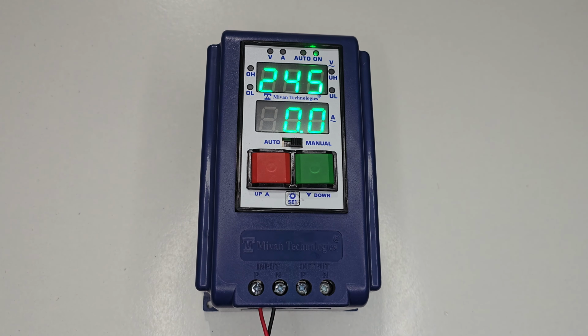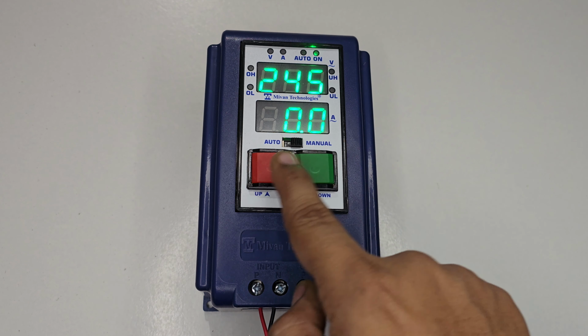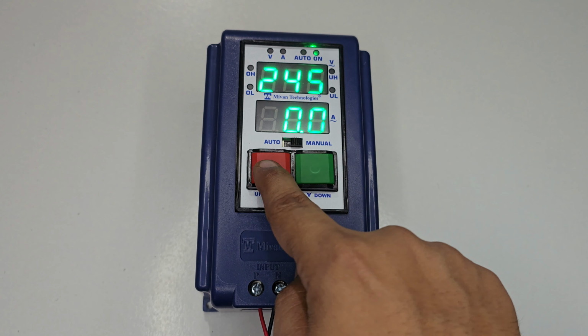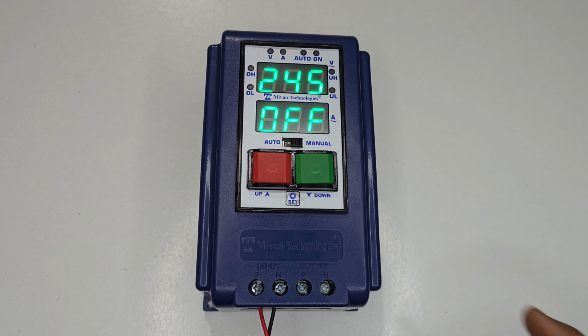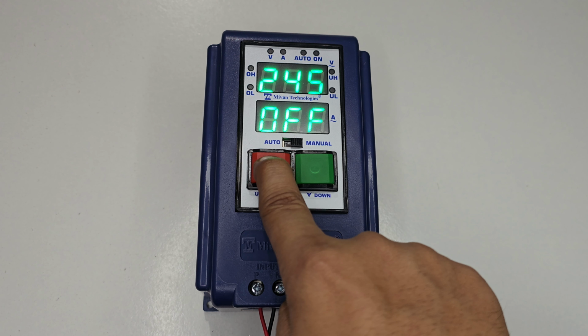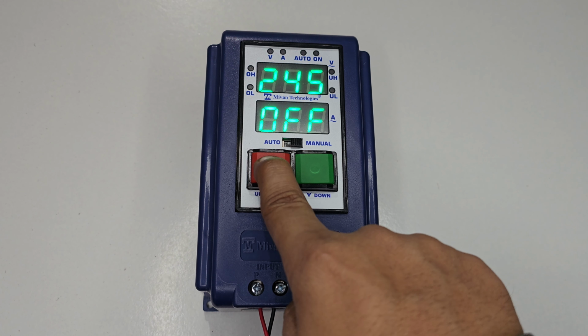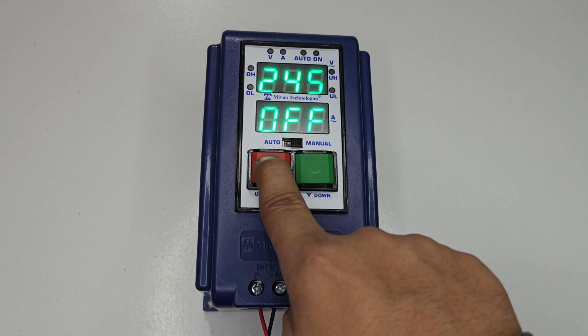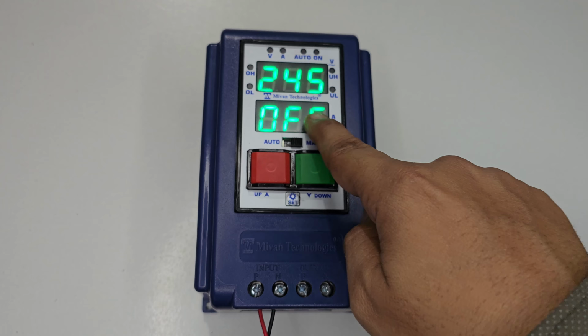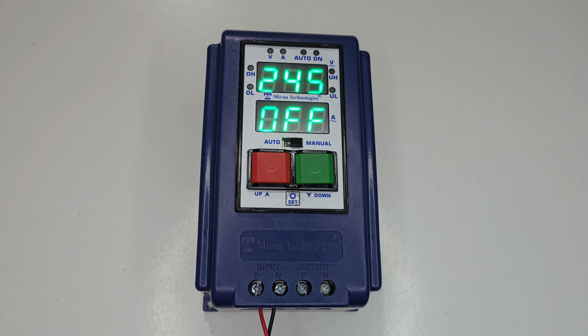In case you have set any wrong parameter, first, if the motor is running, then stop the motor. Then press the red button for 5 seconds to do the factory reset. You can see the factory reset message on the display also. All the parameters are set as per the factory default.